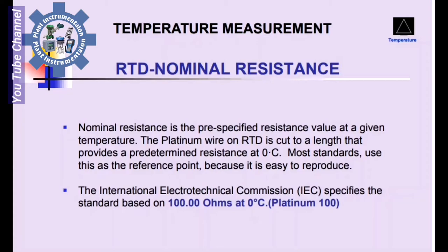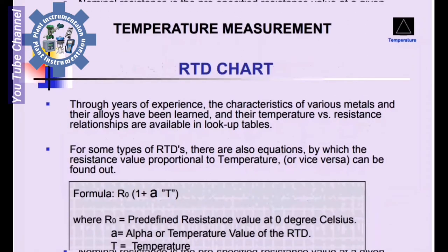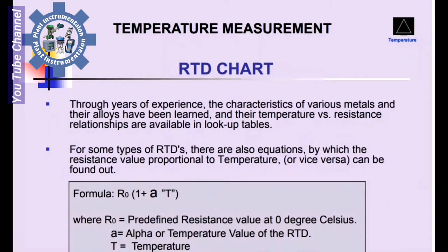Most standards use 0°C as the reference point because it is easy to reproduce. The International Electro-Technical Commission (IEC) specifies the standard based on 100 ohms at 0°C for Platinum. Through years of experience, the characteristics of various metals and their alloys have been learned and their temperature vs. resistance relationships are available in look-up tables.